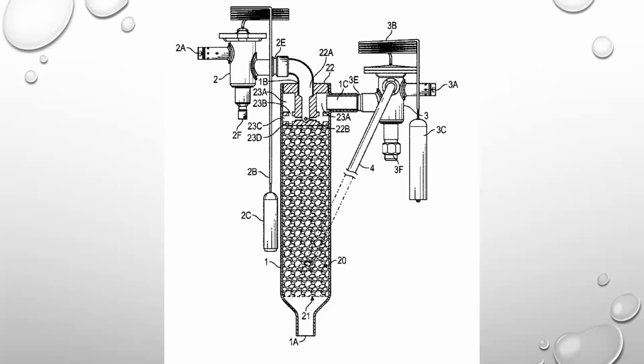The one at the top coming in is a de-superheater valve, which is simply a TXV that shuts off pretty much 100%. And that valve there does have a sensing bulb, and it can be fastened to the body of this device. Unlike a previous device where you had to take the bulb down to the suction line, the top 25% of this valve does the job of a whole other valve. So this only has 3 connections. That makes it pretty easy.